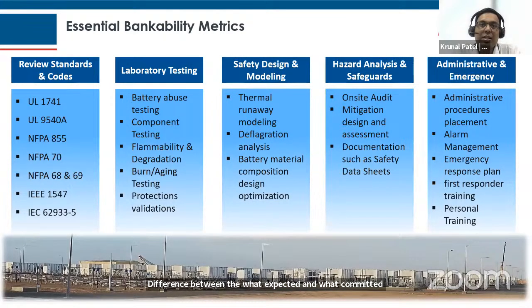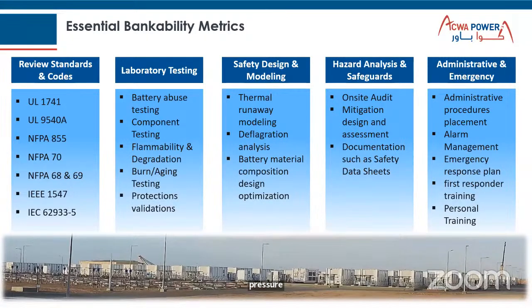Apart from that, safety design and modeling: there are various thermal runaway modeling and deflagration analysis. Deflagration panels are installed in every container, so in case internal pressure builds up, that deflagration panel should open, and there has to be a proper way of operating these panels to avoid any malfunction, as well as to operate during a situation of internal pressure release from the battery cell. Apart...